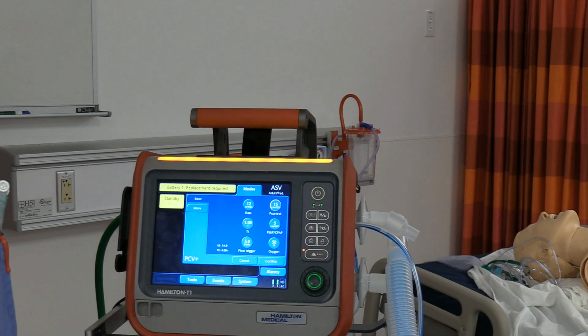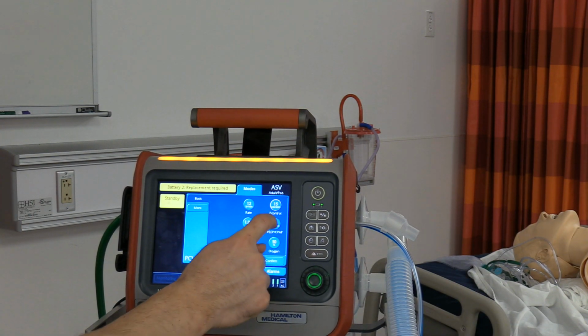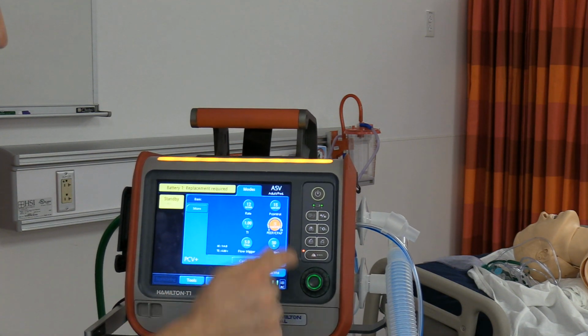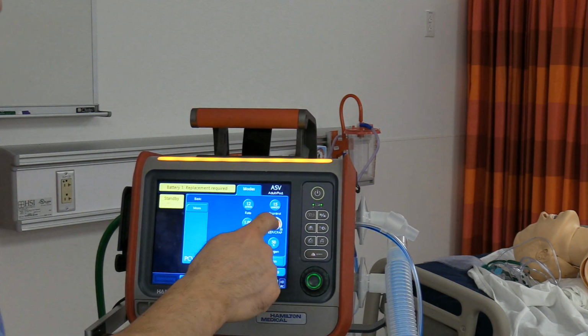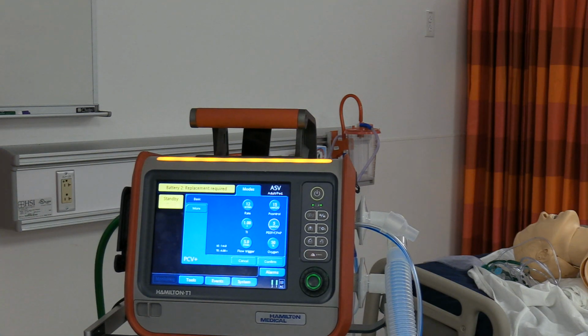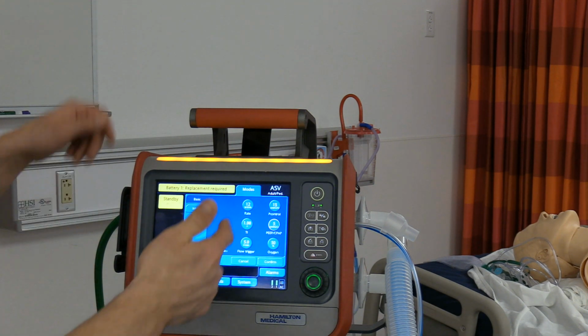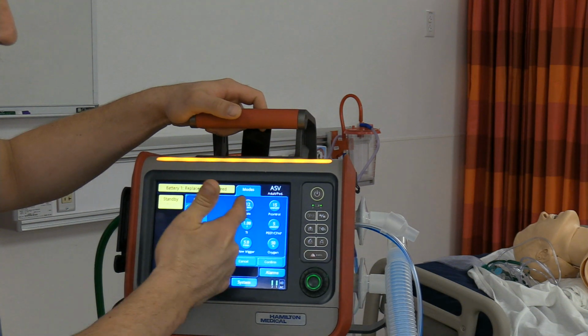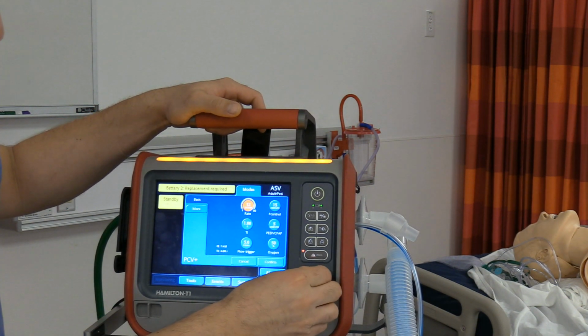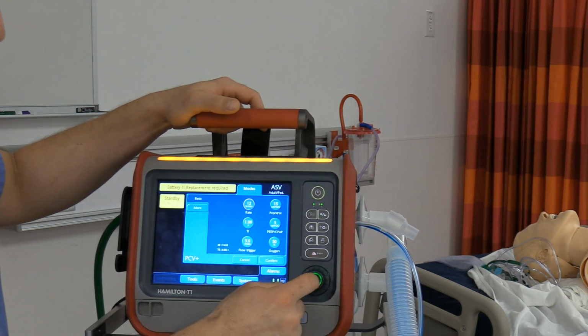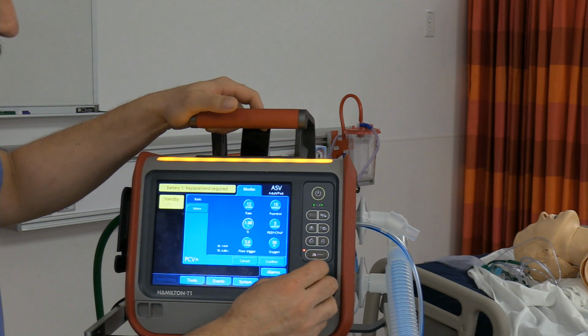P control is our actual inspiratory pressure we're providing on top of our level of PEEP here. Obviously we don't know how much pressure it's going to take if we're initiating ventilation on pressure. I typically start somewhere in that 10 to 12 range and then quickly go up, looking at my exhaled tidal volume. We've got a rate here. Everything is touch screen. You can touch, turn, touch here. I can use this wheel to make changes if I don't want to touch the screen.